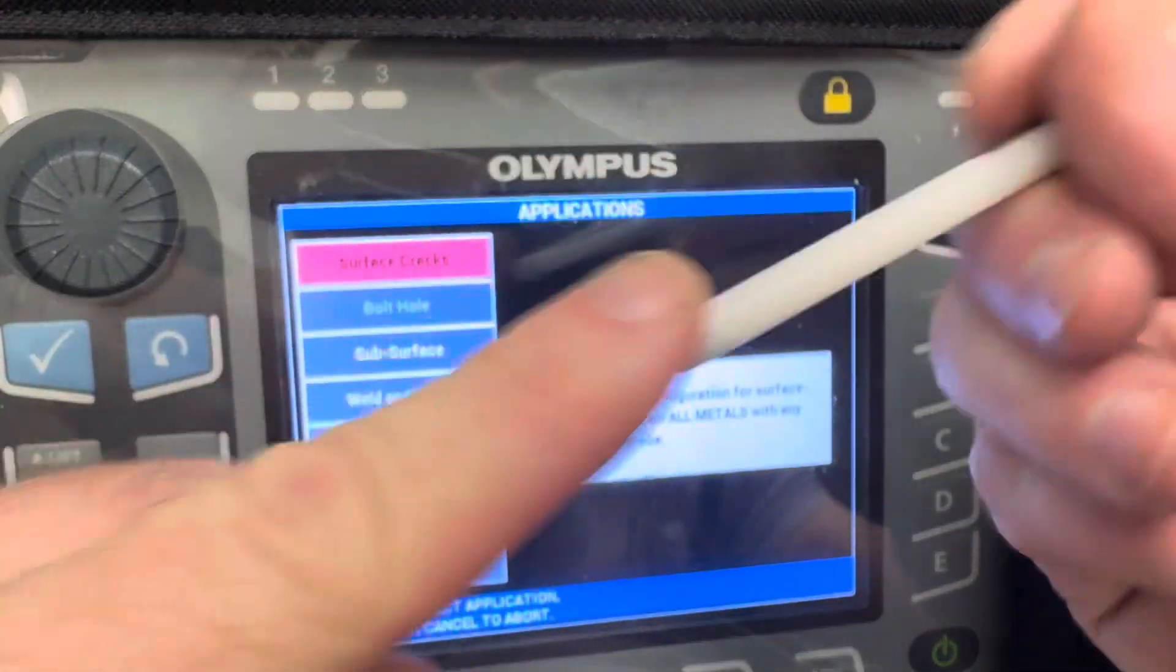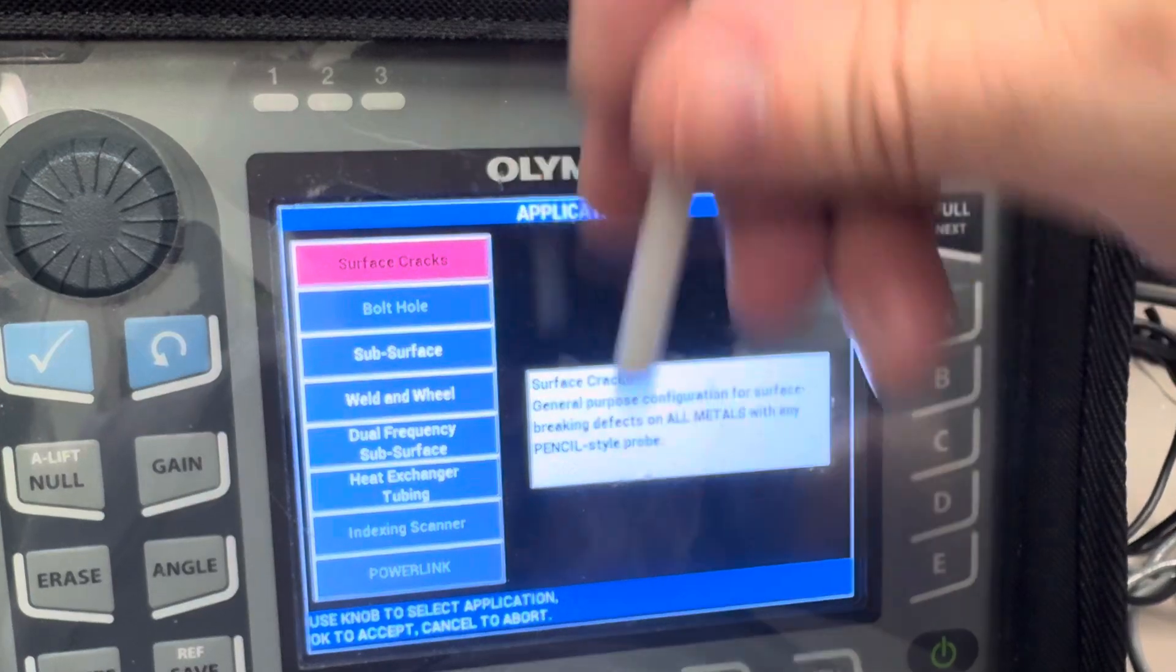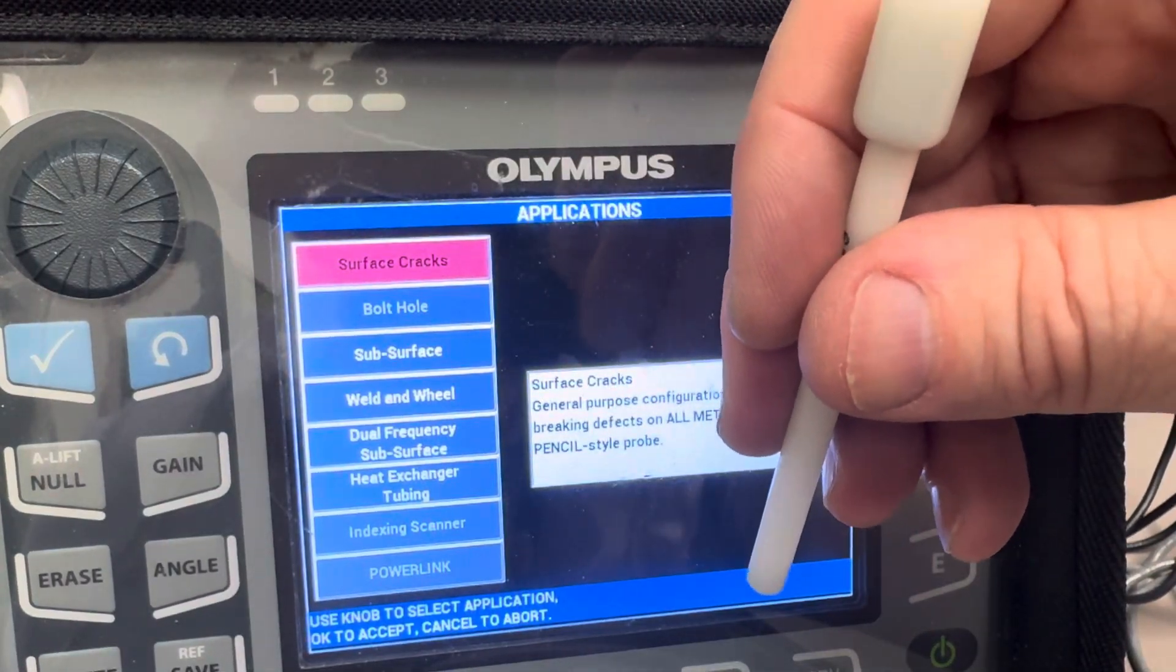With the pancake coil it doesn't matter if you scan this way or that way, just because it's wound in a circle and it's planar. You can scan in any direction, you can still find flaws whether they're axial or transverse. Scan pattern doesn't really matter.